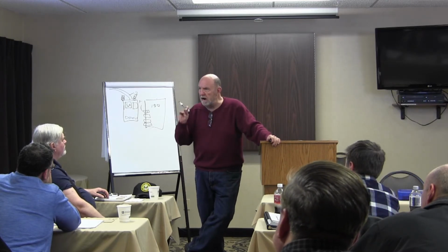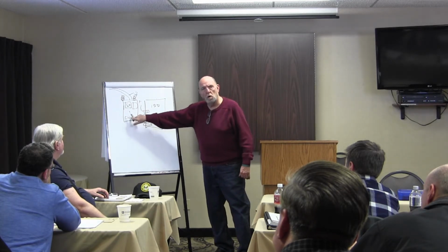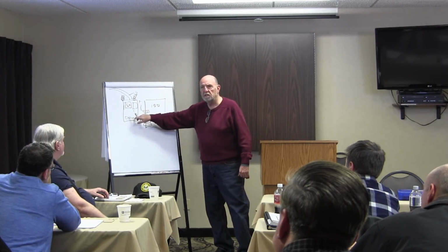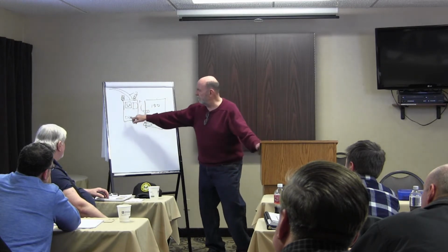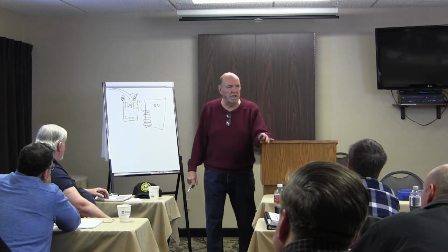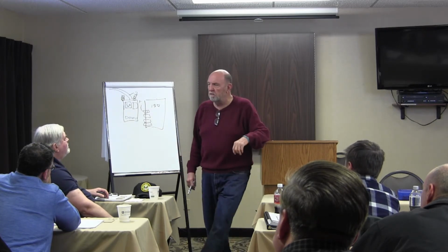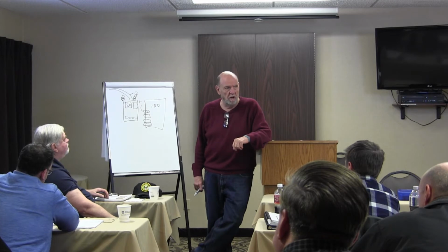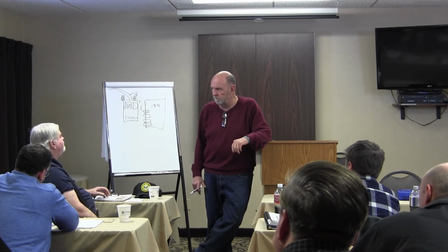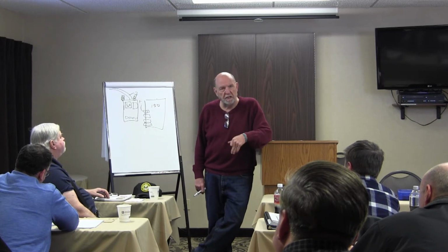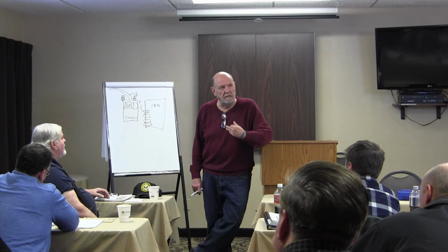So the operator error is the reason insurance companies won't insure a safer system, because too often there's too many cheats to get around the effects of the breaker. So when somebody says, oh my God, my house is going to burn down with the fuse system, no, that's not true. The house is going to burn down because you got stupid. Okay? So, yes, you see a fuse system, you call it out as a defect.